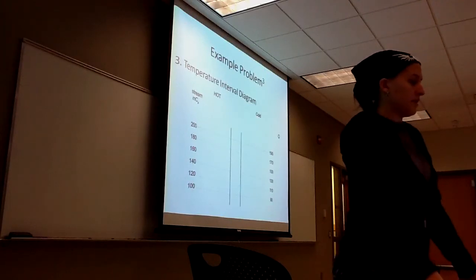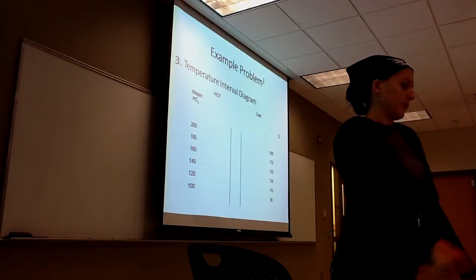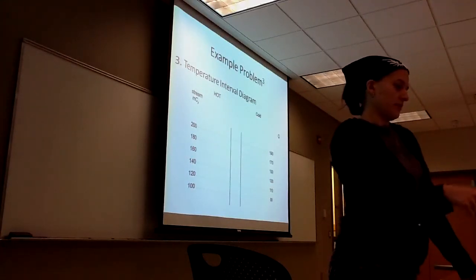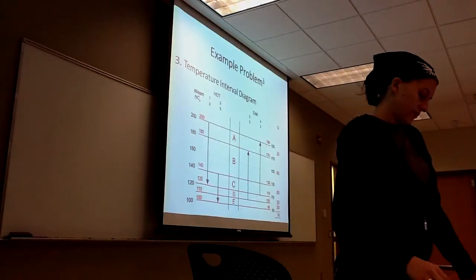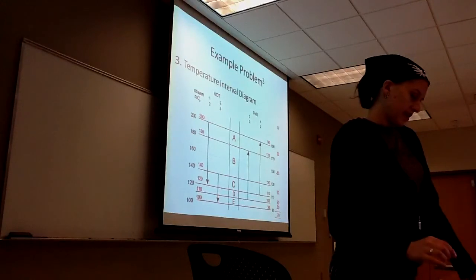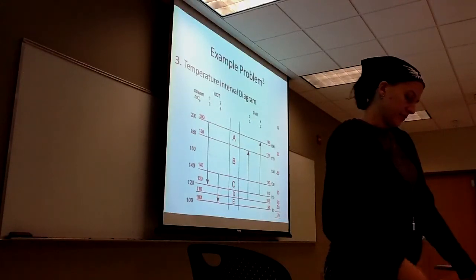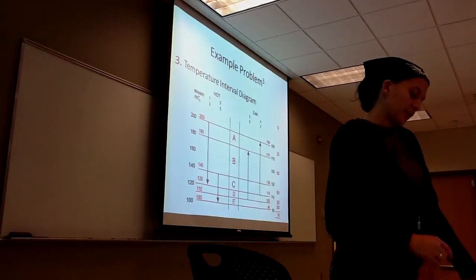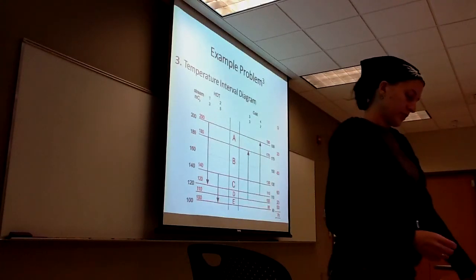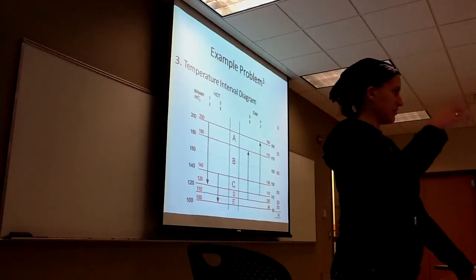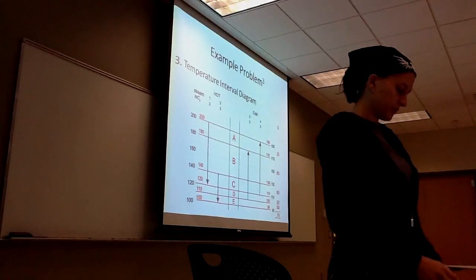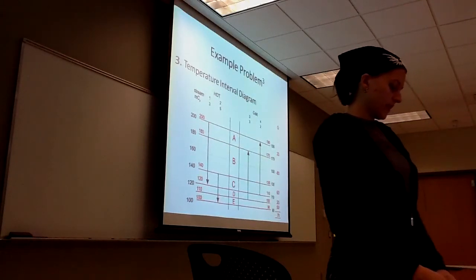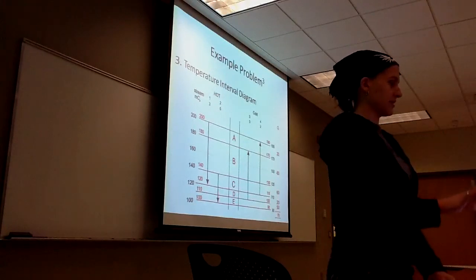It's got your Cp on the left of the stream and the Q on the right, and you fill it in. You start with A for the highest temperature interval, calculate each heat flow for each interval using the Q = M·Cp·ΔT formula that we all know and love so well, and take that sum over all streams that exist in that interval.